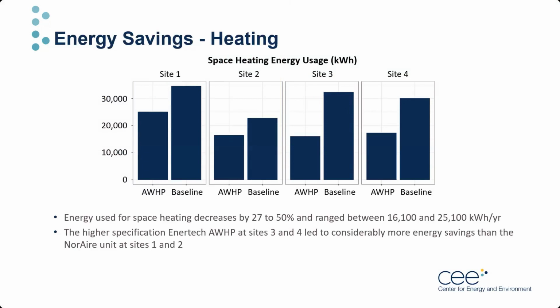Recall that the seasonal COP was 1.35 for the NorAire split system at sites 1 and 2, and up to 2 for the Enertech monoblock at sites 3 and 4. So the higher spec for these monoblock systems does yield higher performance in this case. Overall, we feel like this is quite a good outcome, where the energy savings are between 27% and 50%, or between 16 and 25,000 kilowatt hours per year. A notable takeaway here is that this is in line with our expectations for cold climate air source heat pumps in Minnesota, which we'll loosely define as inverter-driven products that are capable of operating well below freezing. Next slide.